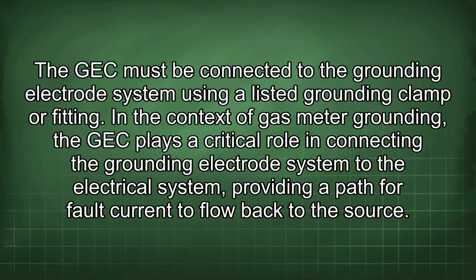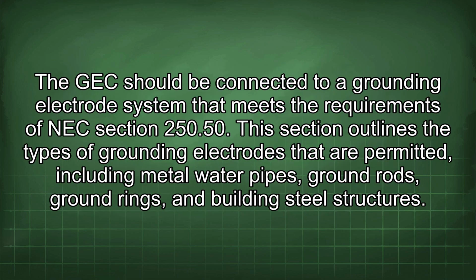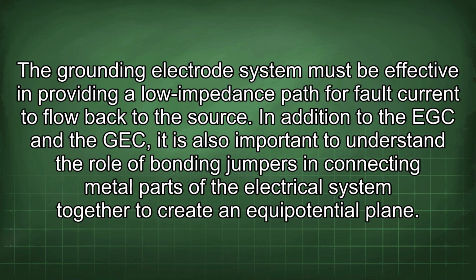In the context of gas meter grounding, the GEC plays a critical role in connecting the grounding electrode system to the electrical system, providing a path for fault current to flow back to the source. The GEC should be connected to a grounding electrode system that meets the requirements of NEC Section 250.50. This section outlines the types of grounding electrodes that are permitted, including metal water pipes, ground rods, ground rings, and building steel structures. The grounding electrode system must be effective in providing a lower impedance path for fault current to flow back to the source.